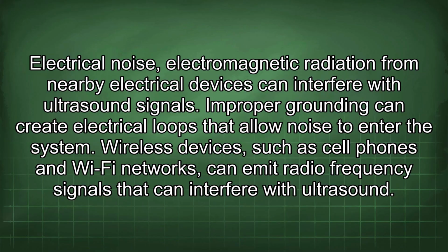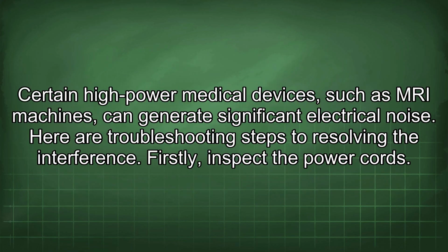Electrical noise. Electromagnetic radiation from nearby electrical devices can interfere with ultrasound signals. Improper grounding can create electrical loops that allow noise to enter the system. Wireless devices, such as cell phones and Wi-Fi networks, can emit radio frequency signals that can interfere with ultrasound. Certain high-power medical devices, such as MRI machines, can generate significant electrical noise. Here are troubleshooting steps to resolving the interference.